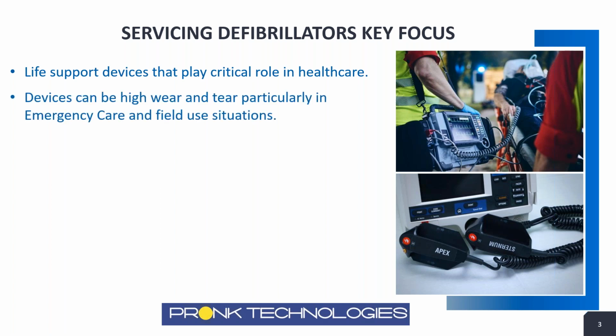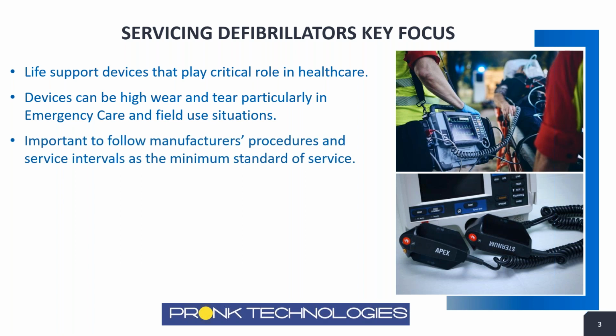These devices can be really high wear and tear devices, depending on their use. Of course, they're used throughout healthcare, particularly in emergency care and field use situations. These devices can be subject to a lot of physical handling that can cause some functions to really wear out or be damaged because of the use in emergency care and field situations. So it's really important that we follow the manufacturer's procedures and the service intervals as our minimum standard of service.